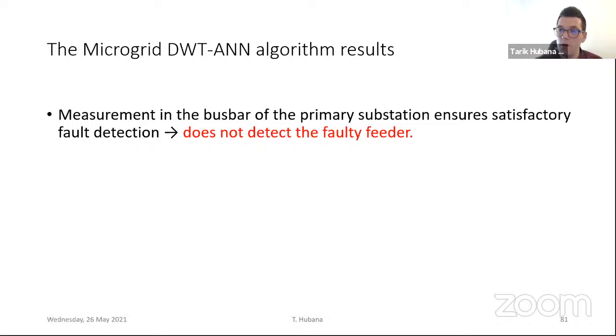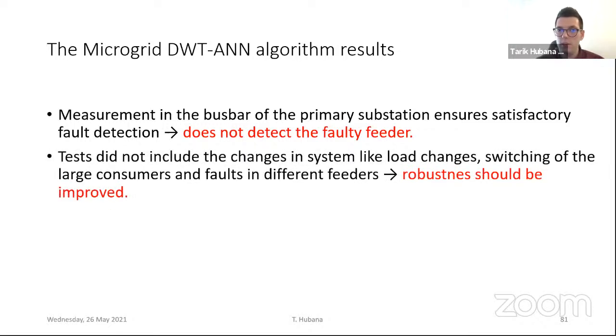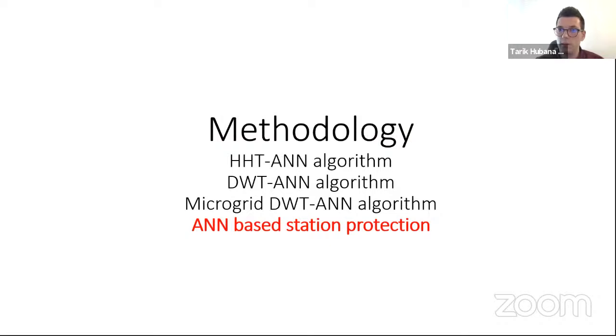signals are important. So the measurement in the bus bar we presented in this research ensures satisfactory fault detection, but it does not detect the faulty feeder. These tests also did not include the abrupt changes in the systems, like the load changes, switching off large consumers, capacitors, or faults in different feeders, which meant that the robustness of this method should be improved. All of these assumptions actually led to the final research, which is actually ANN-based station protection.